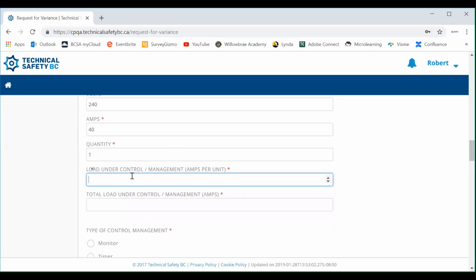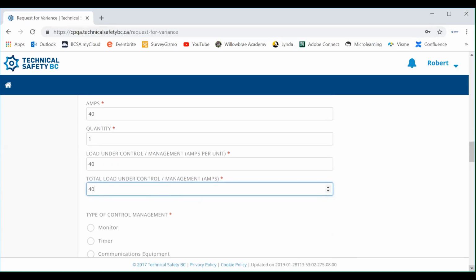Load under control management, amps per unit. We already discussed that the Bosch is drawing 40 amps, so we're going to put 40 there. Since there's only one EVSE, the total load under control is going to be 40 amps. But if in the event that we were using, say, 2 or 3, total load would become 80, or of course 120 for 3, but again, we're just using 1, so the total load under control is going to be 40 amps.